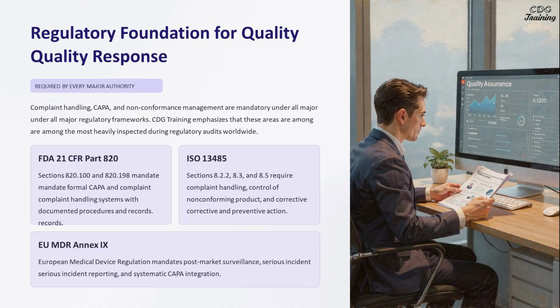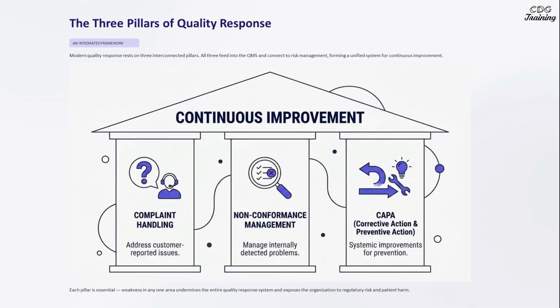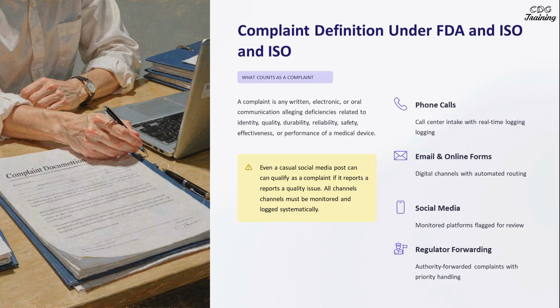Complaint handling, CAPA, and non-conformance management are mandatory under all major regulatory frameworks. These areas are among the most heavily inspected during regulatory audits worldwide, ensuring compliance and quality assurance. Modern quality systems rest on three essential pillars: complaint handling, non-conformance management, and CAPA. Together, they form a unified system for continuous improvement, addressing both customer-reported and internally detected problems. A complaint is any written, electronic, or oral communication alleging deficiencies related to identity, quality, durability, reliability, safety, or performance of a medical device. All channels must be monitored and logged systematically.